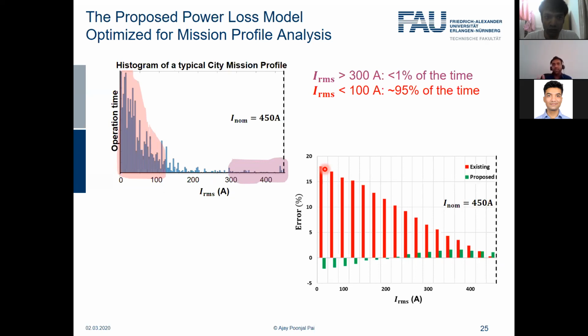I fully understand why these methods are optimized for the nominal point, because the goal of such methods is to dimension the inverter for the nominal point. But this is not suitable for mission profile analysis, because as we see here, the mission profile is mostly in the light load region, so such a method would not be suitable.